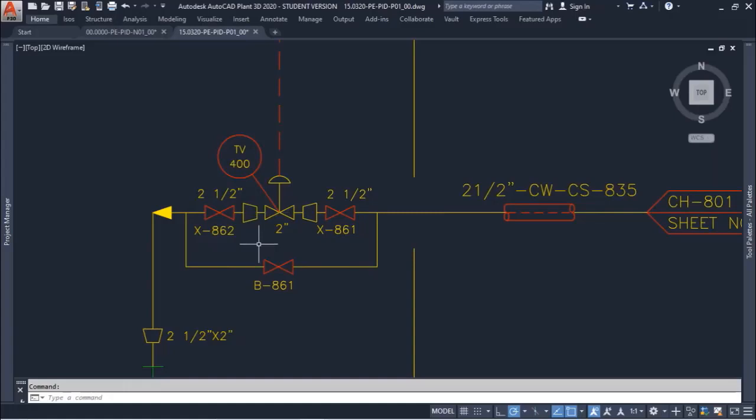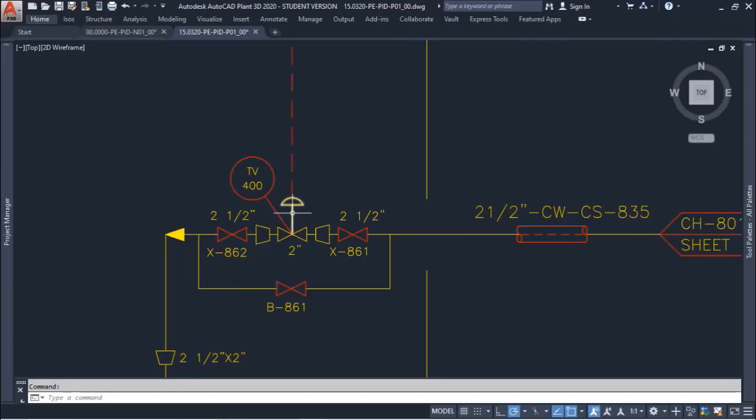to go to the control valve data sheet or specification data sheet. We don't have the information about the signal range, but as it is a control valve, and this is the representation of a diaphragm, it also needs instrument air, although it is not shown in the P&ID.